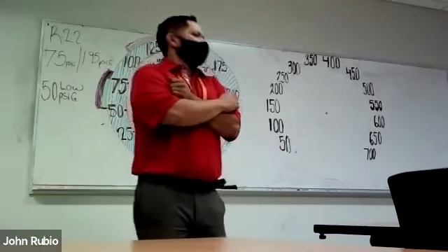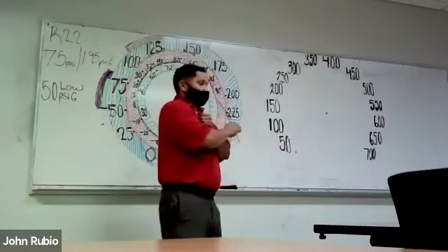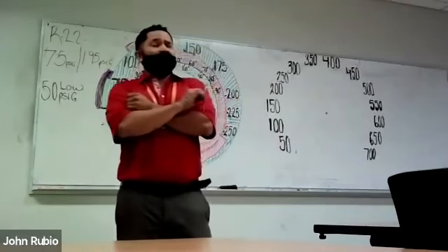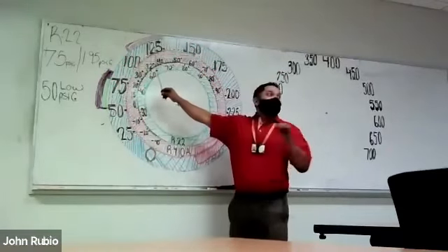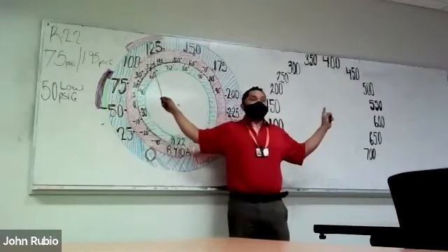We're not trying to tune it, we're not trying to balance it. We're not even trying to see if it has refrigerant, or if it's running low. We're just trying to see if there's refrigerant in it at all. So in a case where the system's off, it's acceptable to just plug in your low side. Once you turn on the system, once the system is on, your high side needs to go on.